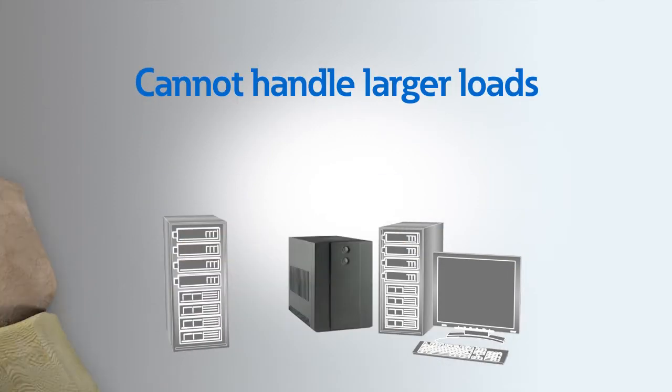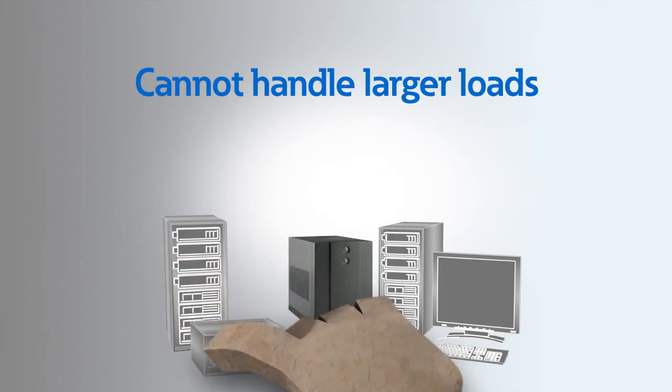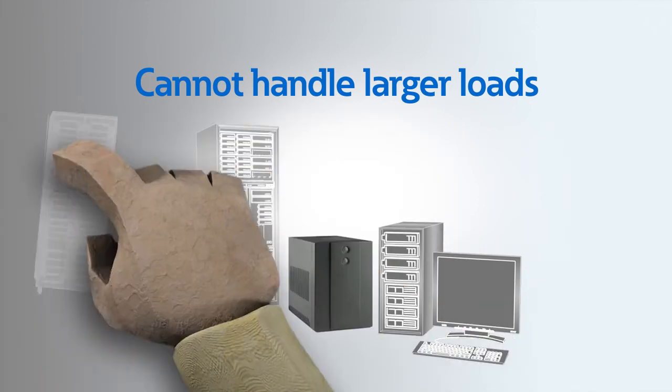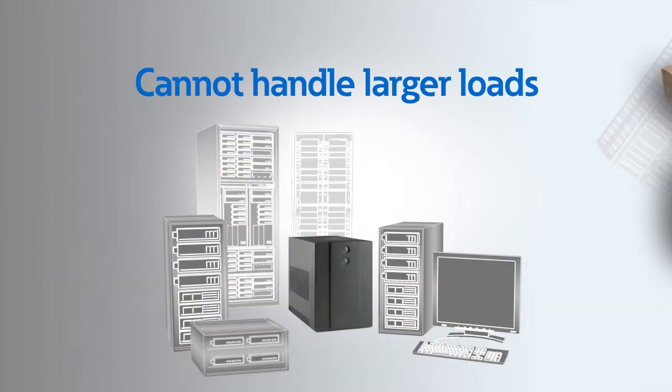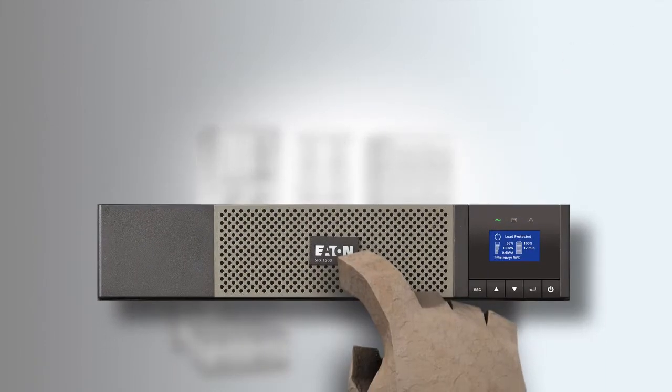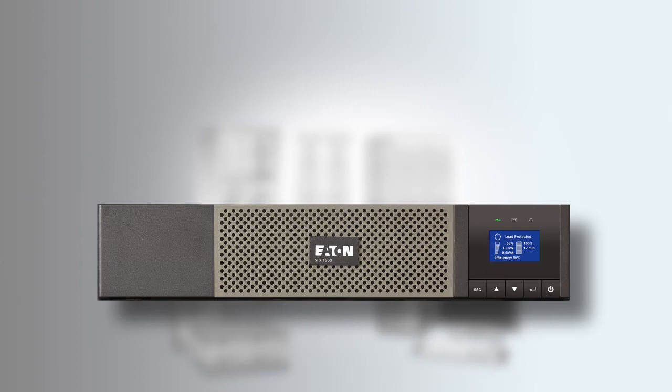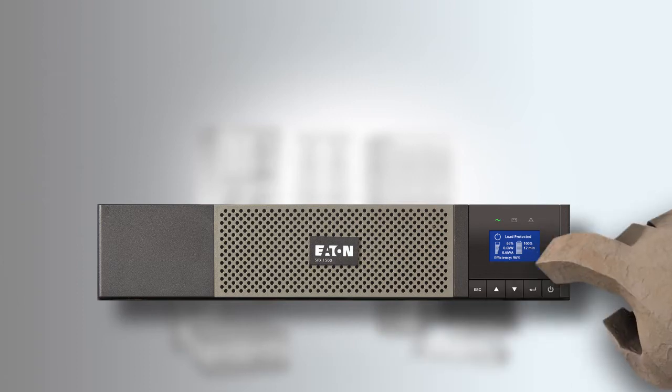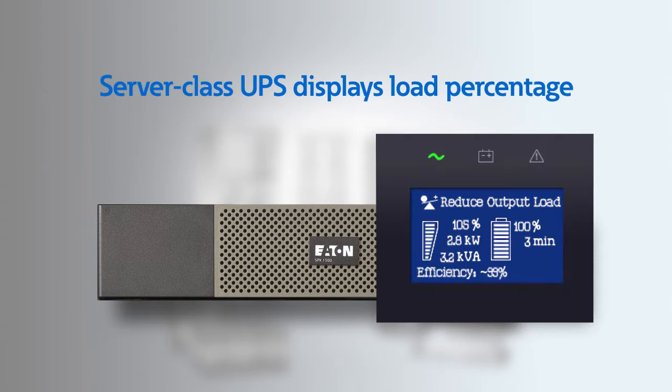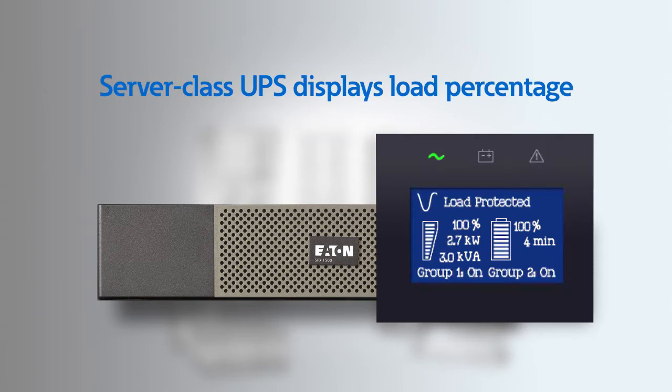In today's world, as equipment is frequently added, you run the risk of overloading your UPS. However, with a server class UPS, you can accurately determine how much equipment can safely be added based on the load percentage information displayed on the LCD menu or through a webcard.